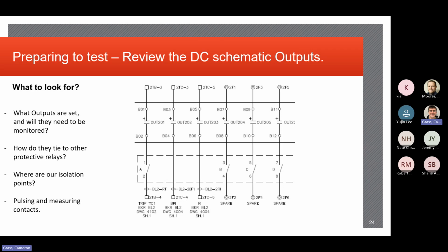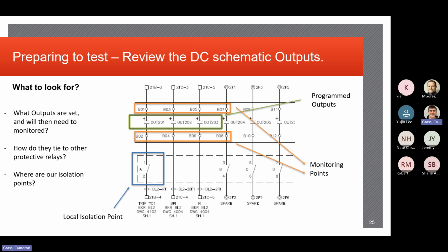Let's see. Okay, so outputs from the relay, monitoring those in our test set. Like I said before, you're identifying your local isolation point, you're verifying that the output picks up when it needs to. How does it tie into other protective relays? Say it's a breaker failure scenario where another relay would be issuing a breaker failure command to this relay. The trip command gets triggered based on that breaker failure initiate, and then vice versa, the breaker failure from this relay triggers a trip elsewhere.